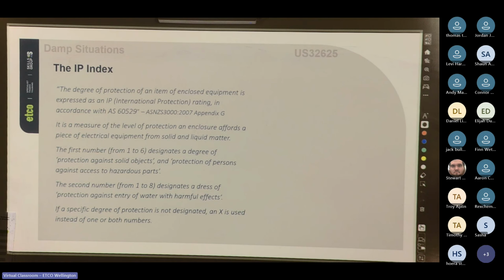So it's a measure of the level of protection an enclosure affords a piece of electrical equipment from solid and liquid matter. The first number from 1 to 6 designates a degree of protection against solid objects and protection of persons against access to hazardous parts. But not just solid objects, but also people. The second number from 1 to 8 designates a degree of protection against entry of water with harmful effects. If a specific degree of protection is not designated, an X is used instead of the number.